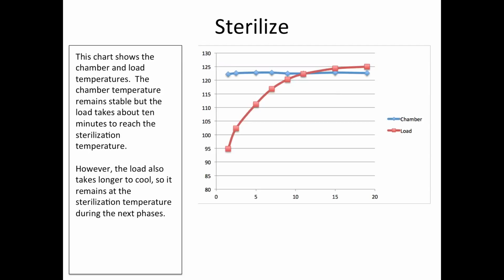This chart shows the chamber and load temperature. The chamber temperature is the blue line on top. You'll note that it is very stable thanks to our jacket charge. But the actual load temperature, the temperature of the water in the flask that's being sterilized, takes a little bit longer to come up to the correct sterilization temperature. Now, the load also takes a little longer to cool, so it will remain at the sterilization temperature during the next few phases.